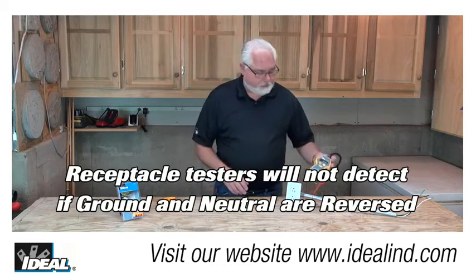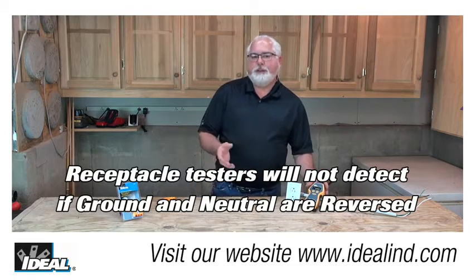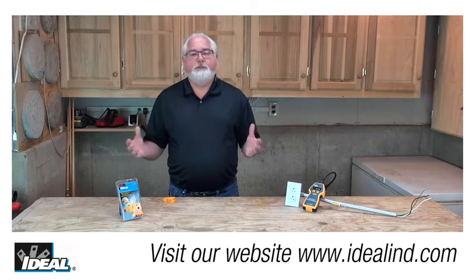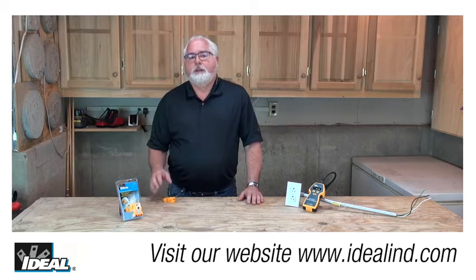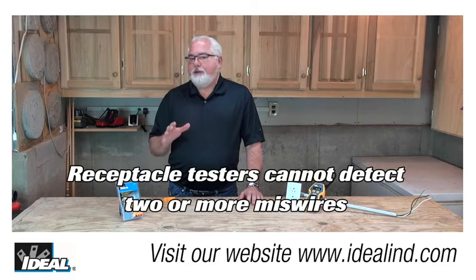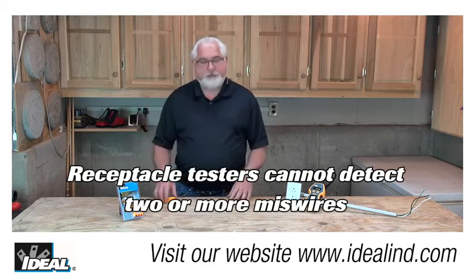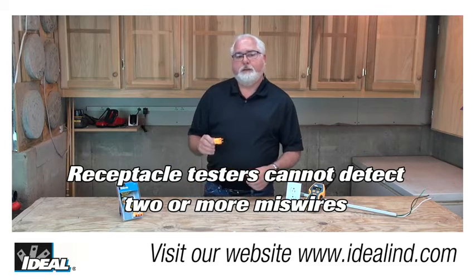And also, receptacle testers cannot tell you if the ground and neutral are swapped, or if there's what they call a bootleg ground somewhere in that circuit. And also, the tester can't diagnose more than 2 miswire issues with the outlet, but it should tell you that there's something wrong and needs to be inspected.